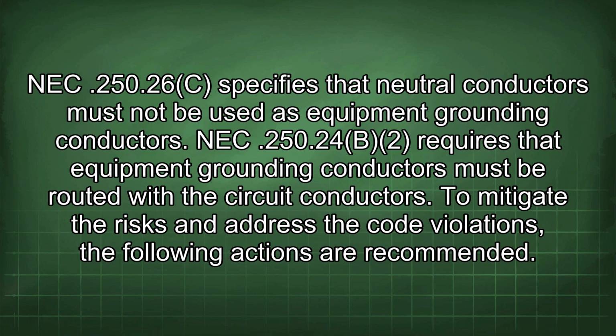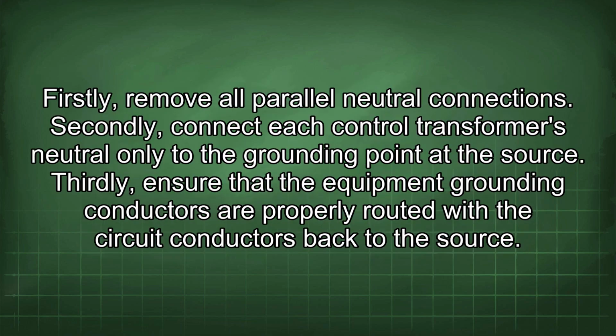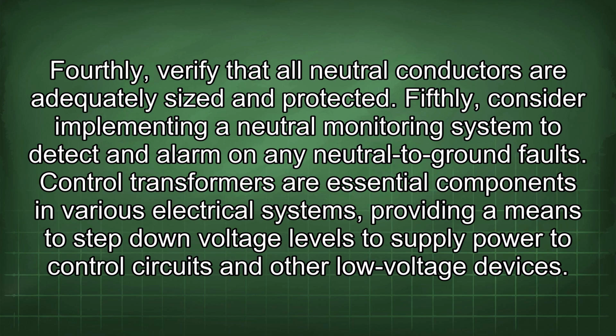To mitigate the risks and address the code violations, the following actions are recommended. Firstly, remove all parallel neutral connections. Secondly, connect each control transformer's neutral only to the grounding point at the source. Thirdly, ensure that the equipment grounding conductors are properly routed with the circuit conductors back to the source. Fourthly, verify that all neutral conductors are adequately sized and protected. Fifthly, consider implementing a neutral monitoring system to detect and alarm on any neutral to ground faults.